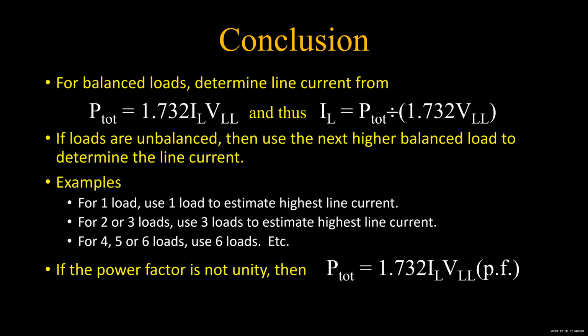And of course, the power, if you have a power factor involved, and we weren't, I mean, they call them volt amps, so that implies a power factor. But the power factor doesn't imply that we have harmonics or non-sine waves. That just says the current and the voltage are out of phase. But still, the line current, you're going to get this data, and you're basing your calculation on the line current anyway, which is going to be in your data in your installation manual for the charger.